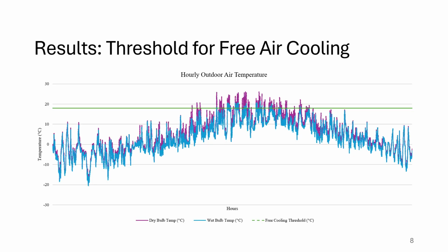To determine the frequency when each mode of cooling will be used, the hourly outdoor air temperature averages for St. John's was simulated over a period of a year. The green line on the graph shows the threshold, which is 18 degrees Celsius, and below this threshold, free air cooling will be used. Above the threshold, mechanical cooling will be used. It shows that free air cooling is used during the cooler months of the year, and mechanical cooling is used during the warmer summer months.